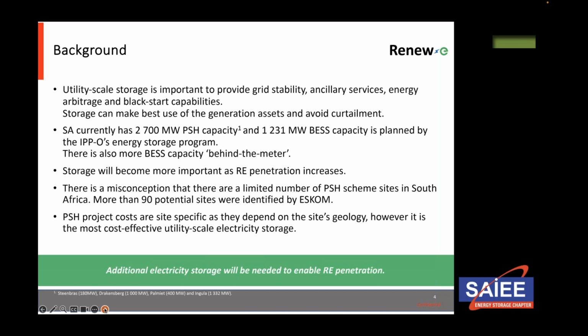Another misconception, not in the slide, is that pump storage requires or consumes a lot of water, because we lump pump storage with hydro. That's inappropriate. Pump storage does not use water, it just pumps water up and down the hill. The water you lose is from evaporative losses and losses through geological faults. This is important because pump storage is suitable for an arid country like South Africa, and South Africa has the right topography for it. The costs are very site-specific, depending on the geology, but it's the most cost-effective solution for large-scale storage.